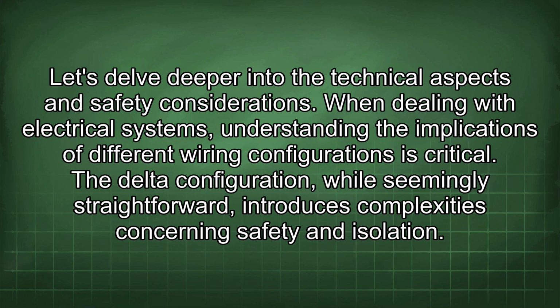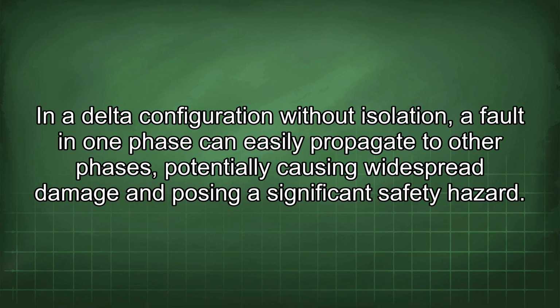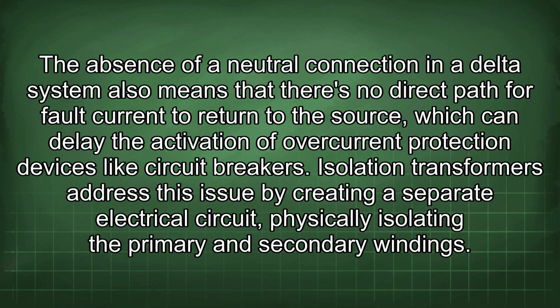When dealing with electrical systems, understanding the implications of different wiring configurations is critical. The delta configuration, while seemingly straightforward, introduces complexities concerning safety and isolation. In a delta configuration without isolation, a fault in one phase can easily propagate to other phases, potentially causing widespread damage and posing a significant safety hazard. The absence of a neutral connection in a delta system also means that there's no direct path for fault current to return to the source, which can delay the activation of overcurrent protection devices like circuit breakers.